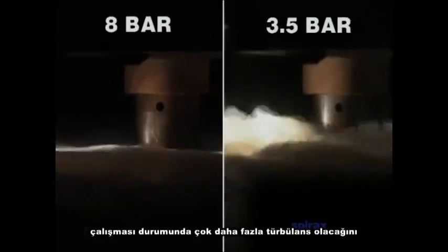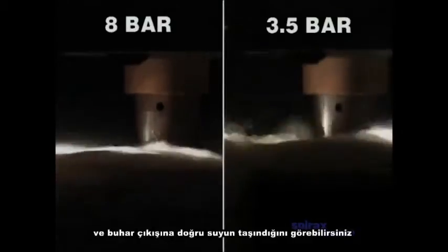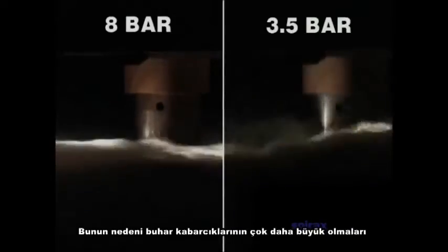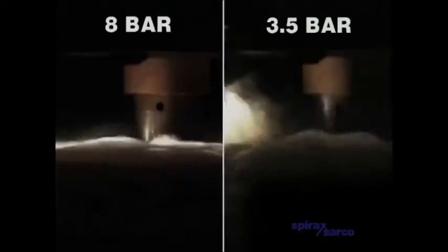If you compare a boiler running at 8 bar and 3.5 bar, but under the same load, you can see that the low-pressure operation is far more turbulent, with water splashing toward the steam takeoff. This is because steam bubbles are larger. Lower pressure and larger bubbles cause more turbulence as they break the surface. Low-pressure operation is obviously less stable, and there is more chance of water droplets contaminating the quality of steam when the water level is at a high point.